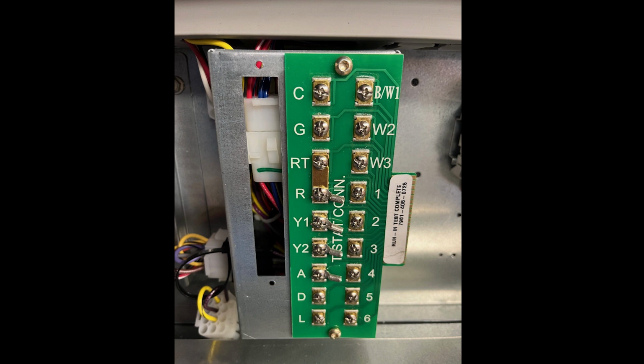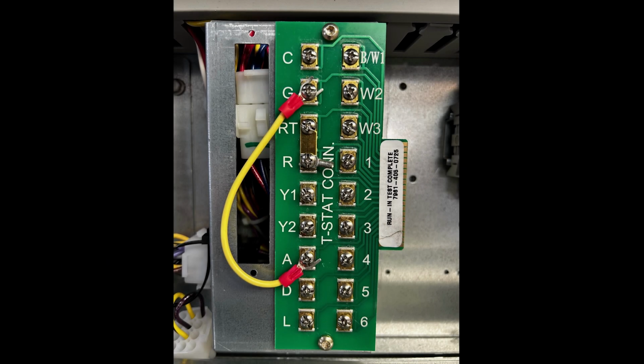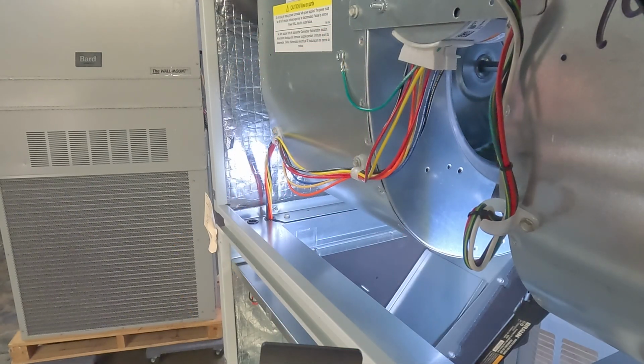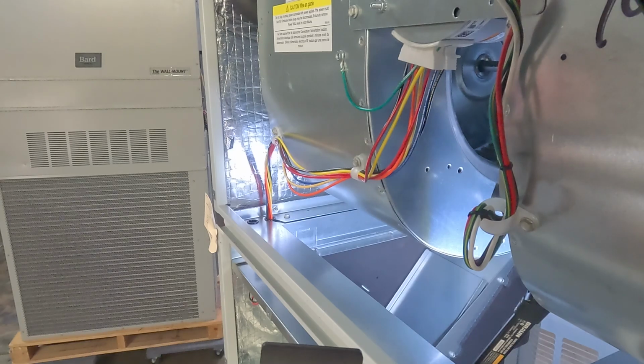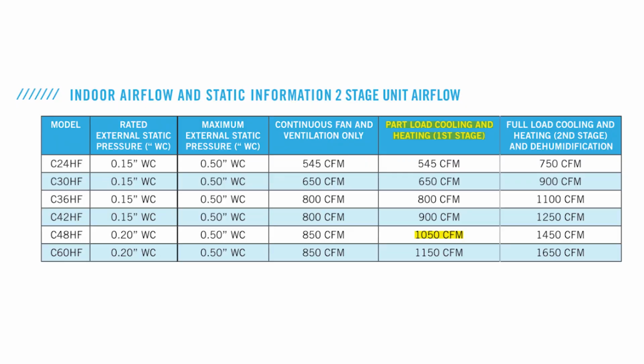If you want the damper to open when G is energized with comfort conditioning, do not energize A separately on the low voltage terminal block. Instead, add a permanent jumper from G to A. This would be a constant ventilation method during occupied times. The CRV operates, open and closed, the same for a single stage or two-stage compressor unit. Understand the ventilation CFM will be less on first stage than second stage of a two-stage unit with a fixed blade on-off damper.